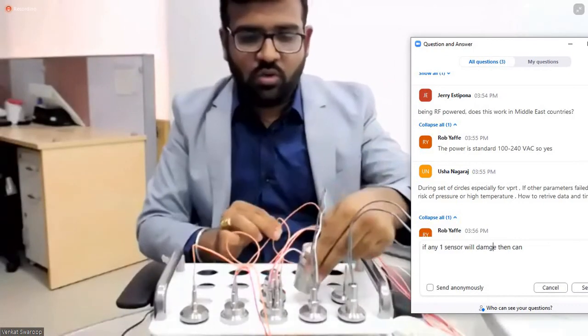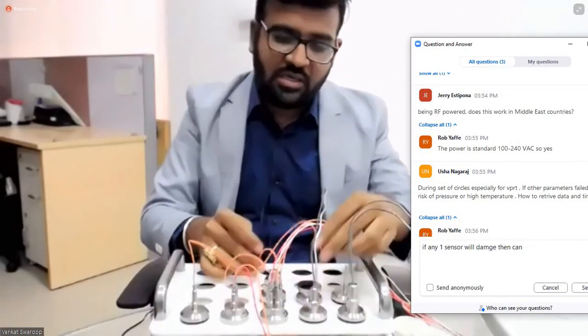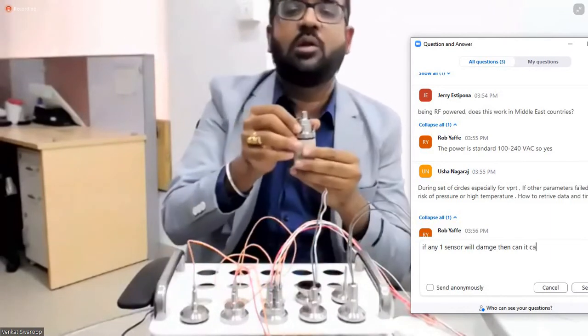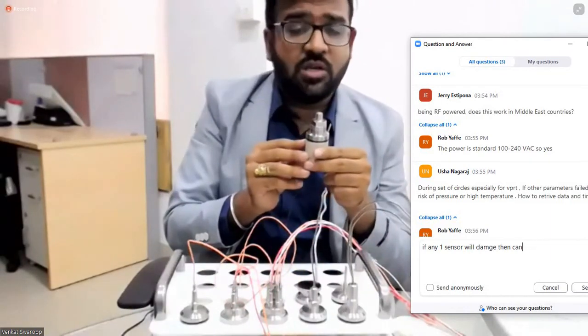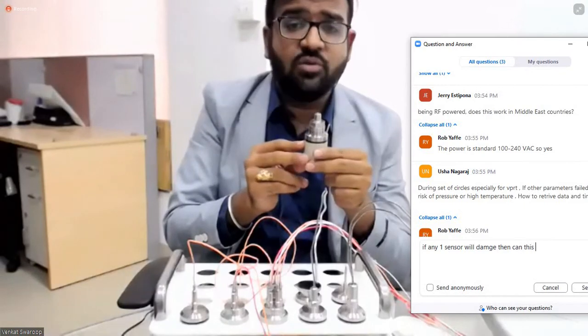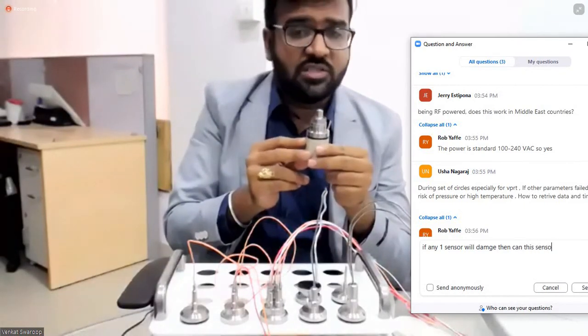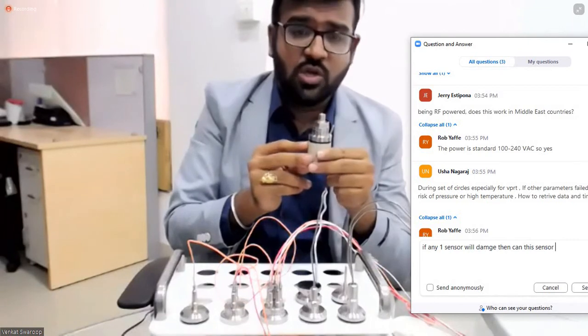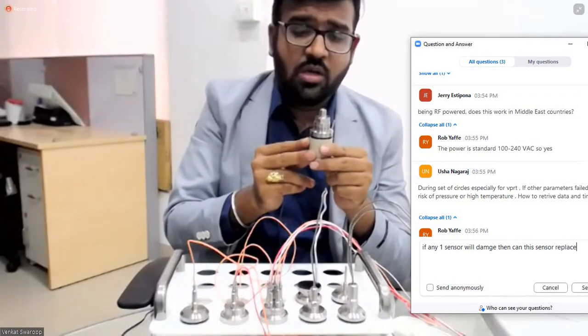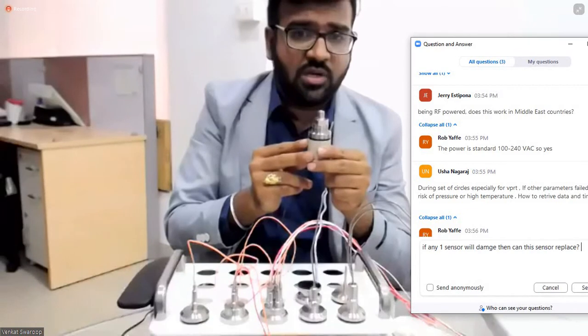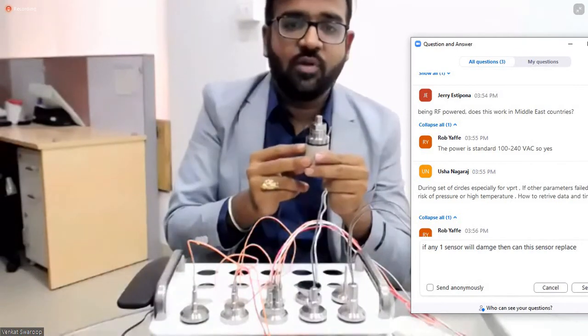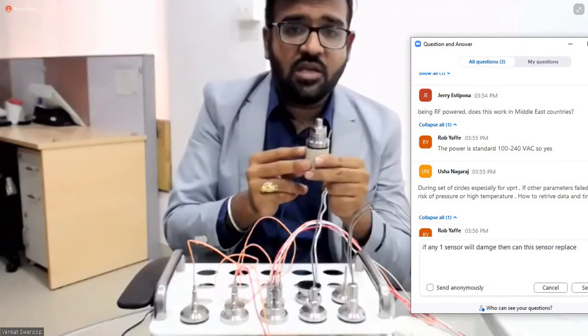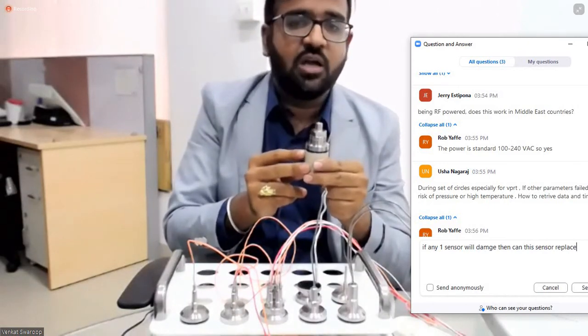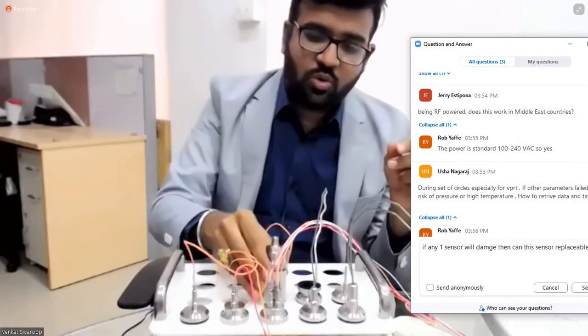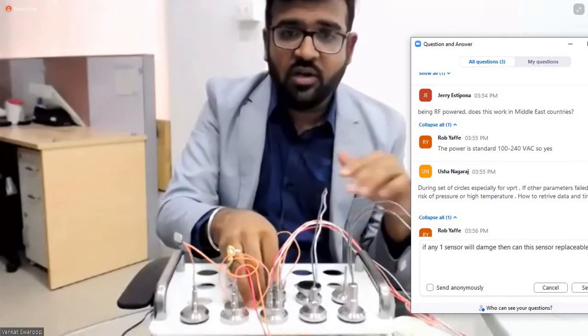Now the last important logger is the pressure cum temperature logger. As you know, pressure is also an important point to consider in steam sterilizer validations and other things. In this combination logger, there is one channel of temperature and one channel of pressure, so it simultaneously records both temperature and pressure values and transmits the data to the base station and console. So this is about all the different loggers.